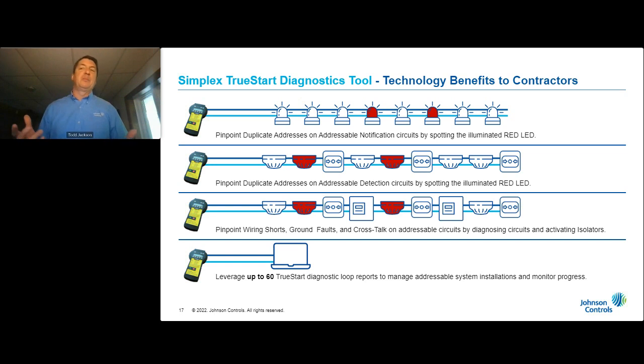Think of the device that we provide. It's like a mini fire alarm panel. It can test all the devices long before your fire alarm panel shows up. And like I mentioned earlier, you don't want to use that expensive fire alarm panel as a piece of test equipment, because if you damage something or blow something up, think about the supply chain issue we're all dealing with. Now you need a card because you didn't test your field wiring properly, or at all, and now you're stuck with a condition that's going to stretch you out of the job and make you late on it.